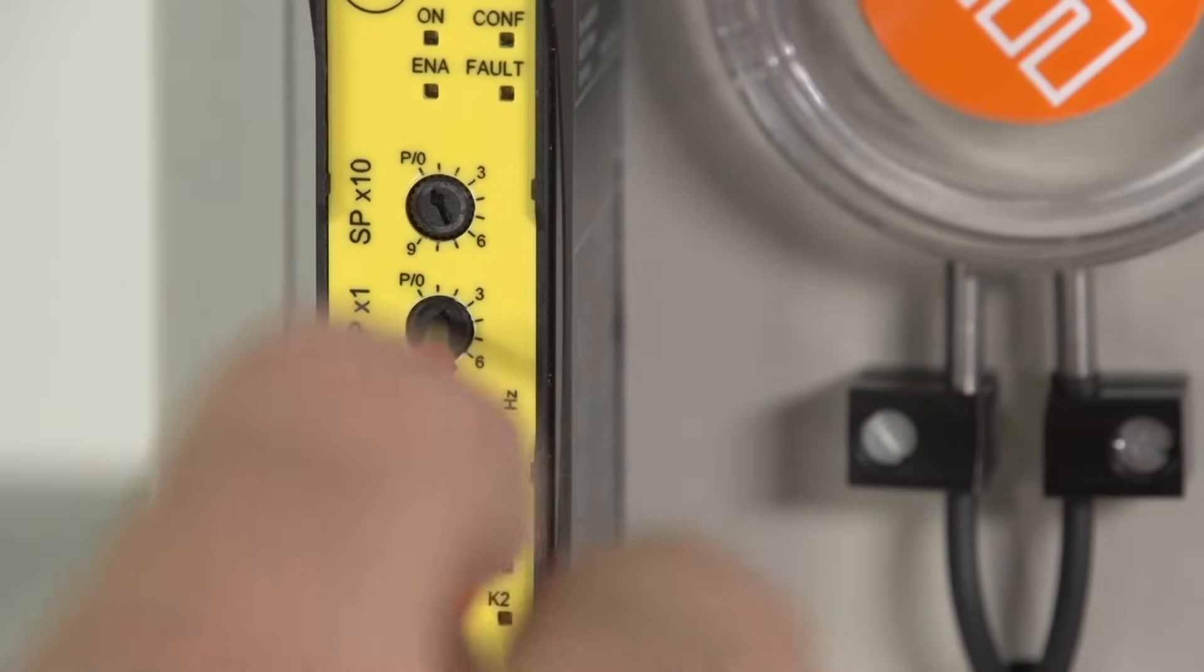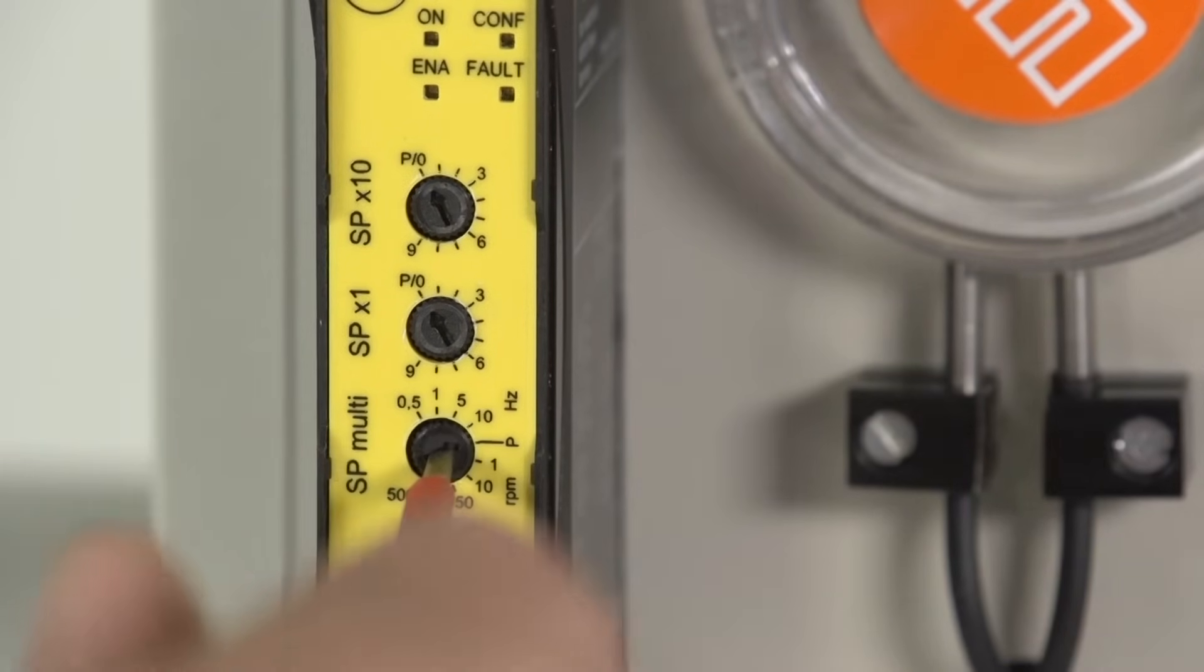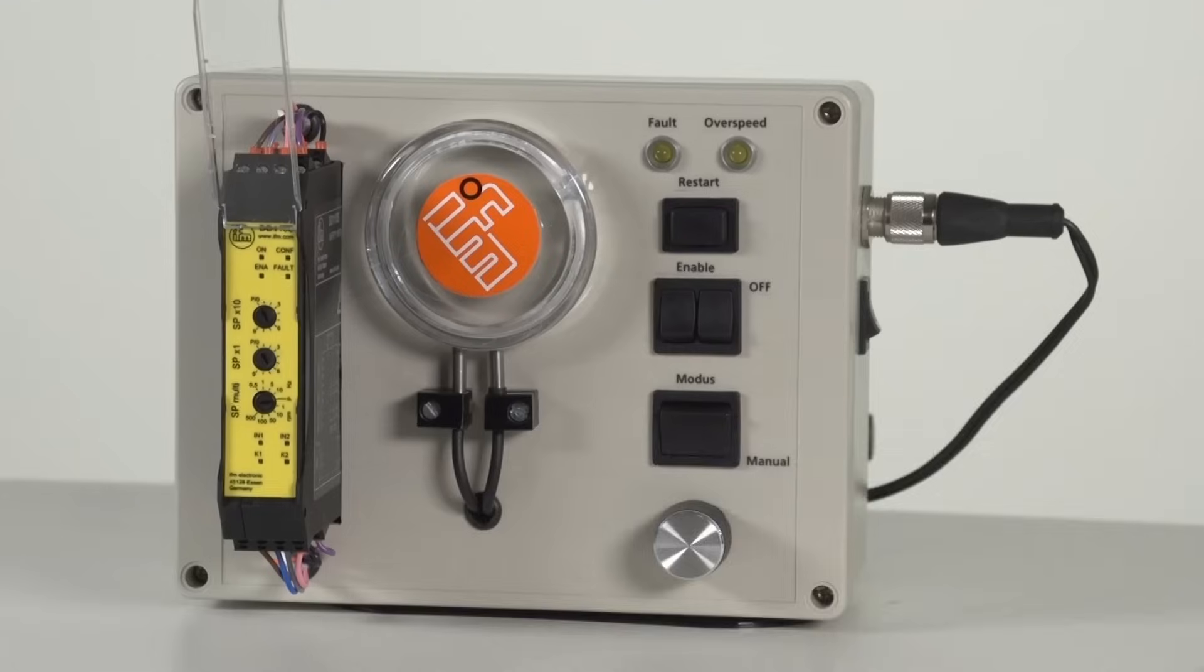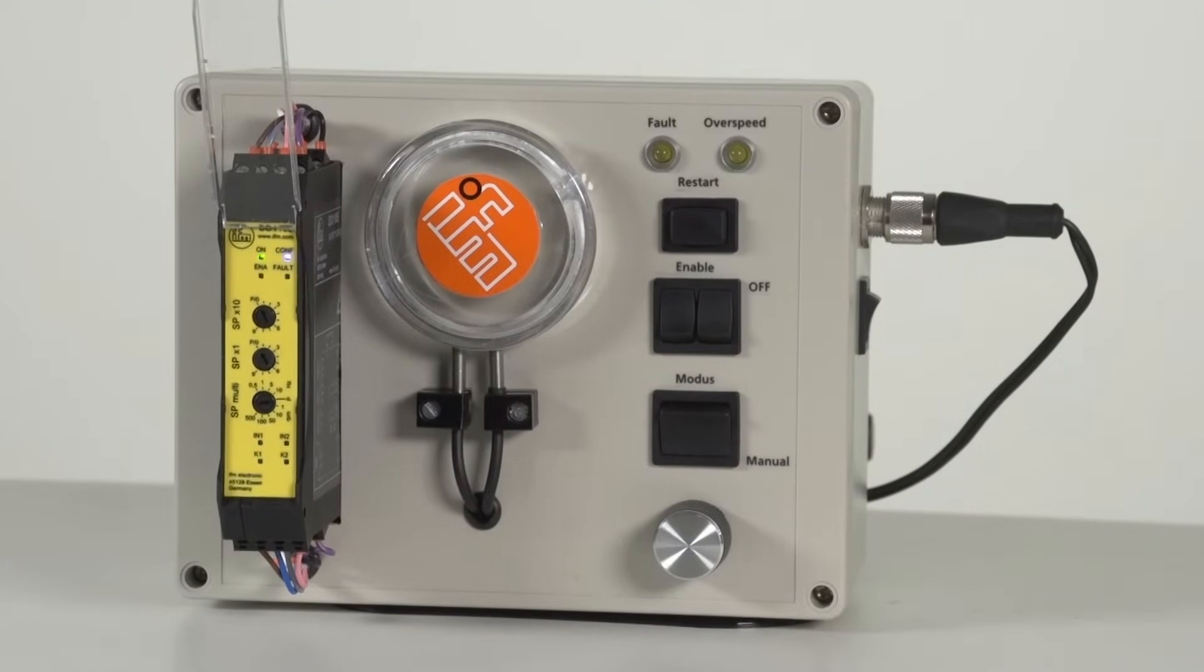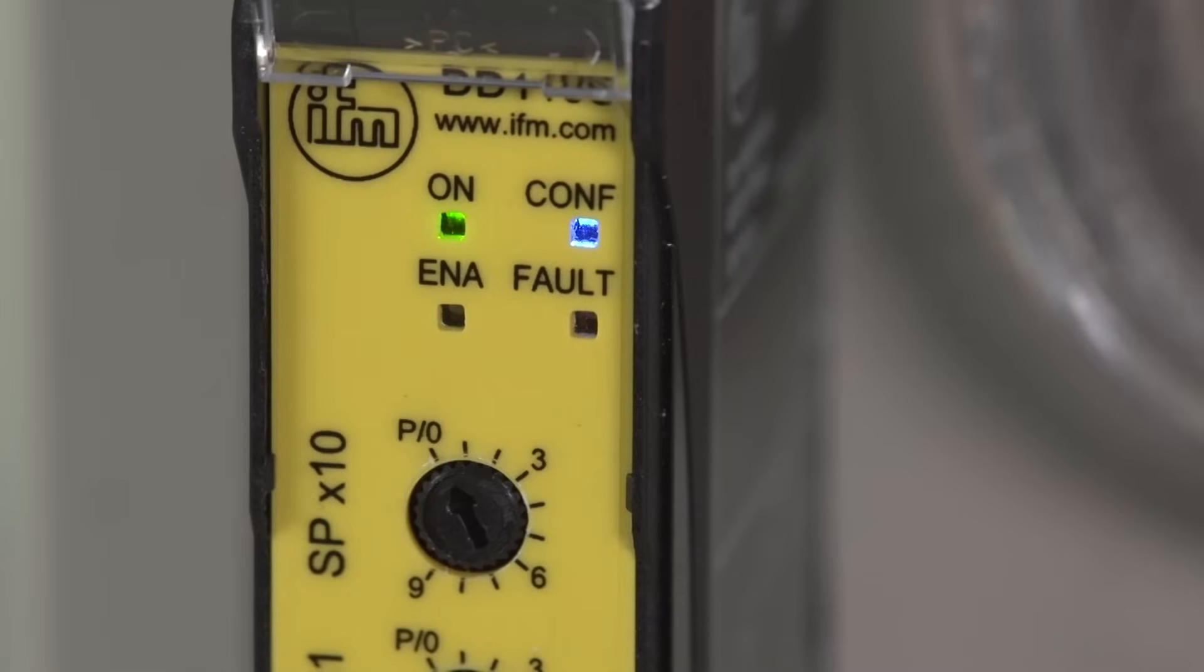When the monitor is switched on for the first time, all three rotary switches must be set to the position P. Then the SAFE speed monitor goes into the configuration mode. This is indicated by the flashing blue LED.